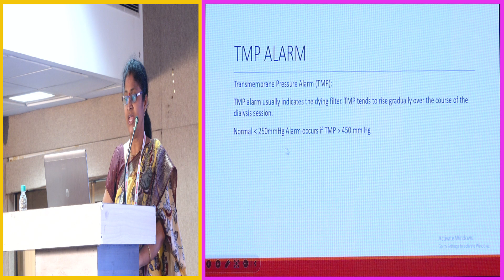So this is the TMP alarm. The normal is less than 250 and we get the TMP alarm only if it is more than 450. This you should remember, because we don't get the TMP alarm immediately; the TMP often starts to rise early, before we get the alarm. This morning we discussed that we are all creatinine centric. So we wait till creatinine rises, we don't initiate this. Similarly, don't be number centric. Don't wait till the alarm comes.